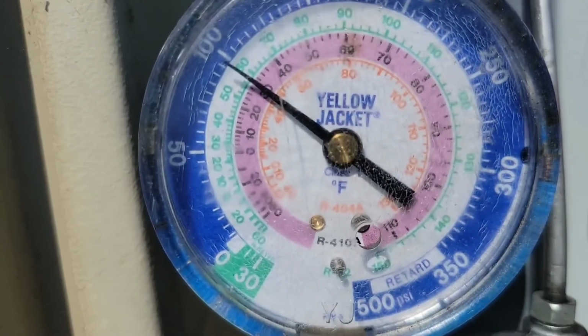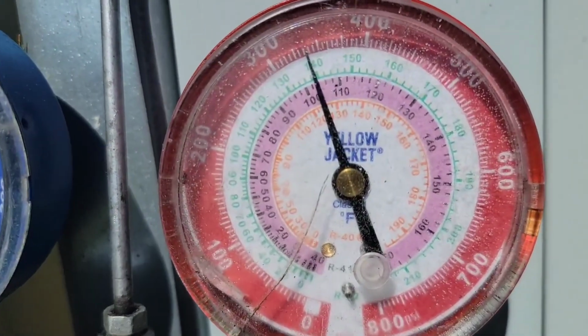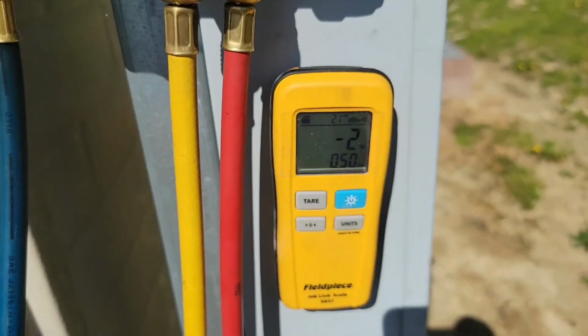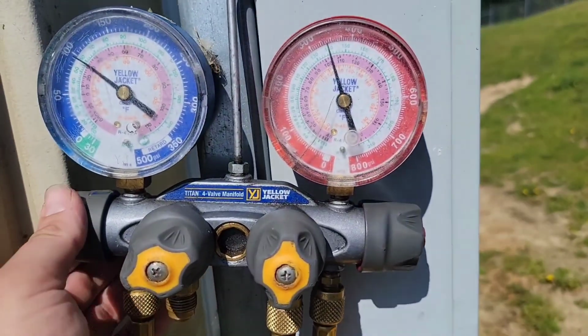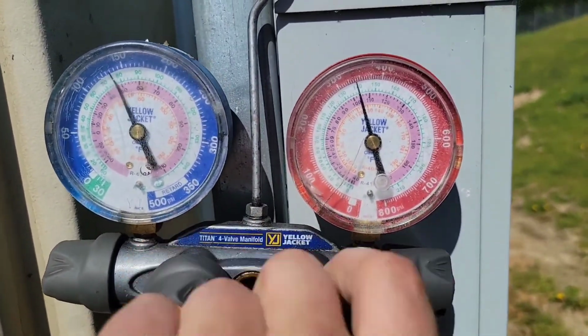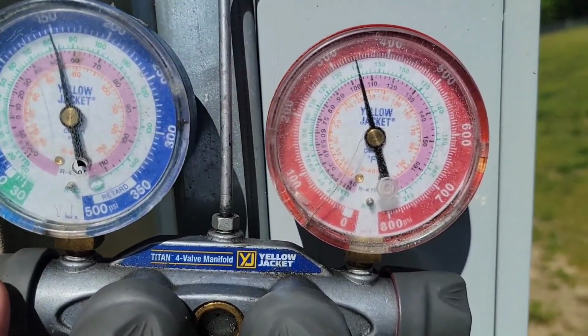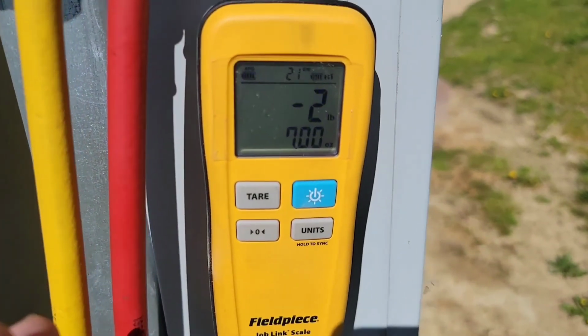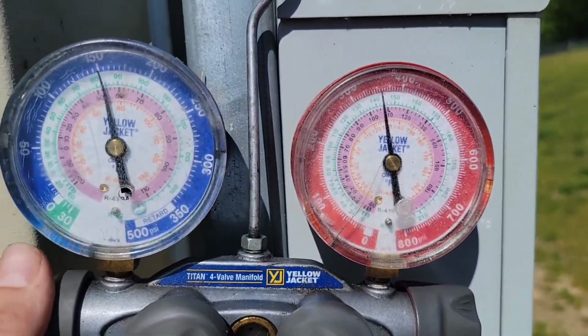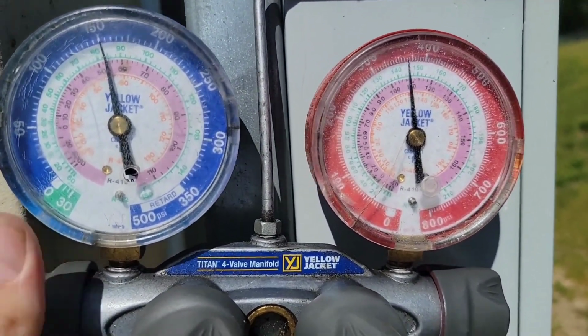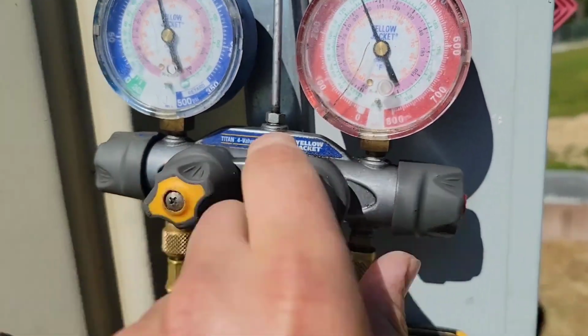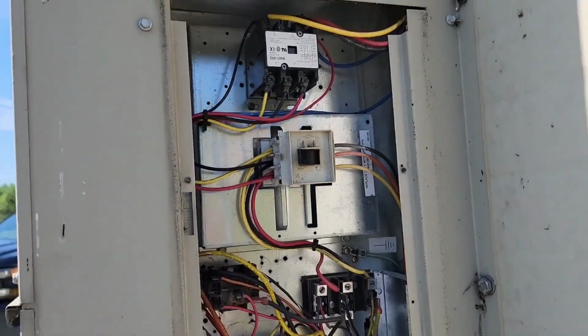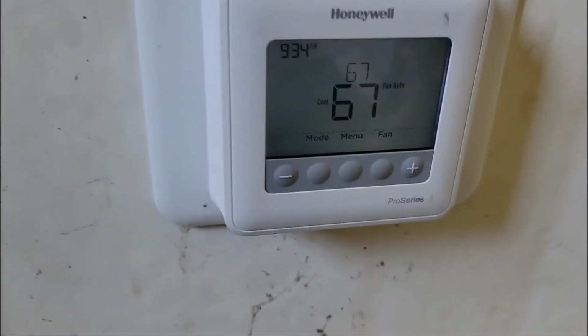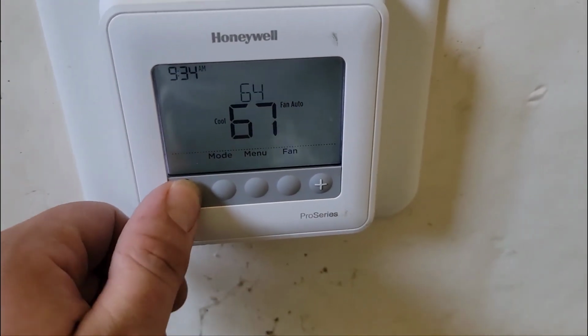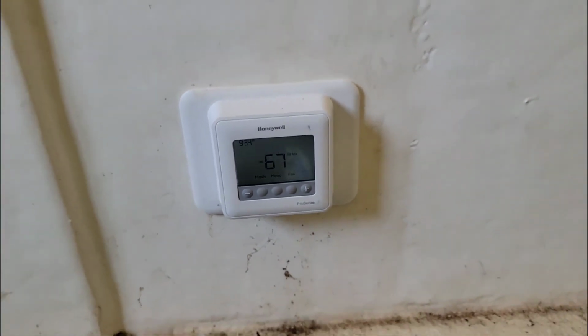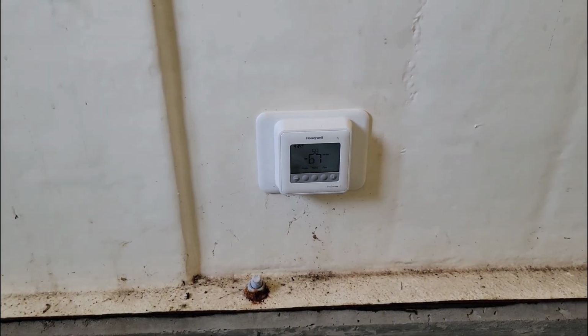Okay. So we've got 95 and about 235, and we're gonna add some more refrigerant. We've only got 2 pounds, so add a little bit more. Then we're gonna check and see where we're at. It's 2.5 pounds. I think we're gonna stop there. Oh, it just shut off. Let's go check the thermostat. Wow, it's already reached temperature. That's excellent. Okay, turn it back down so we can make sure that charge is right.